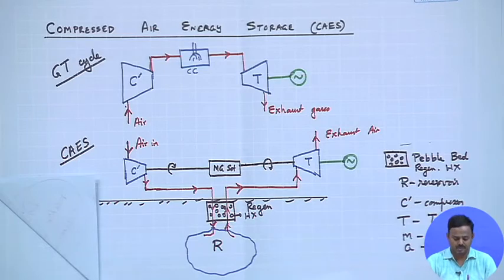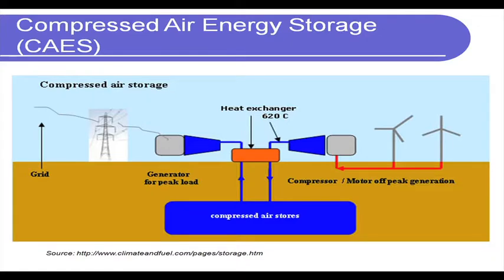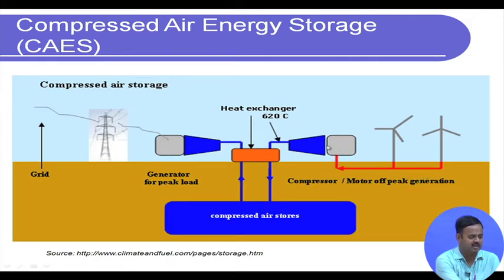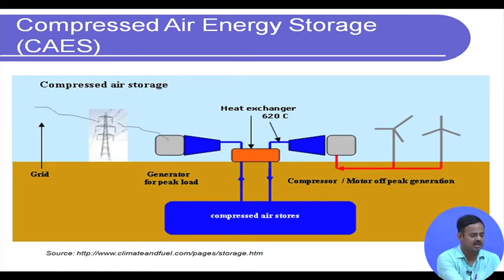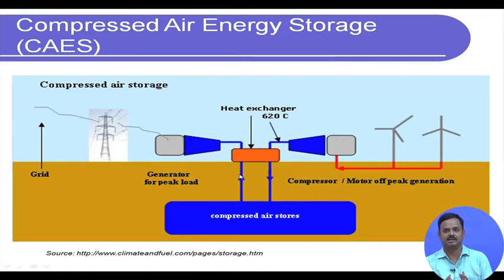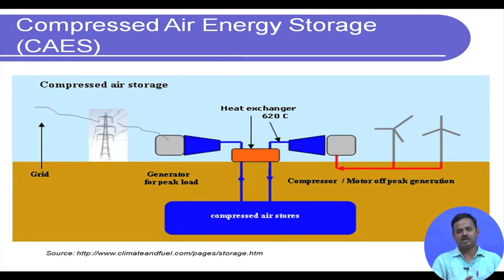To summarize the diagram: during off-peak hours, we have additional generation, so the compressor compresses the air and stores it. During peak hours, the compressed air is fed into a turbine which generates electricity. The heat exchanger must be regenerative because the flow from the compressor and the flow through the turbine do not happen simultaneously, so the heat must be stored and later passed on to the compressed air before it goes to the turbine.